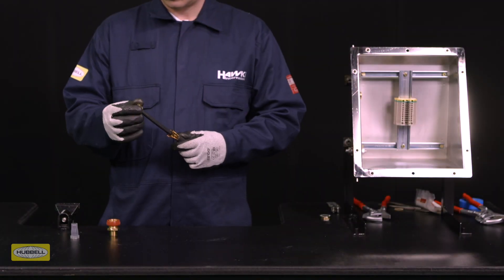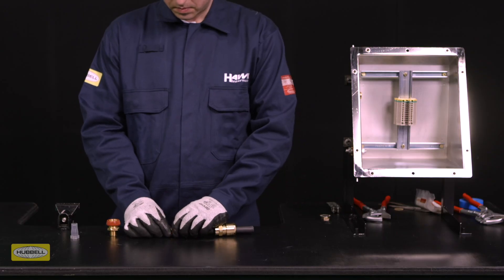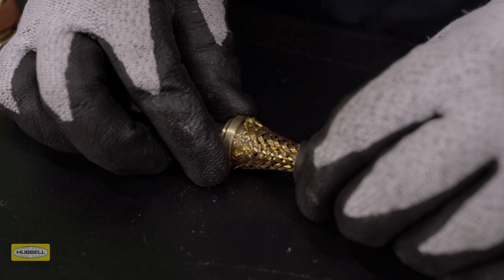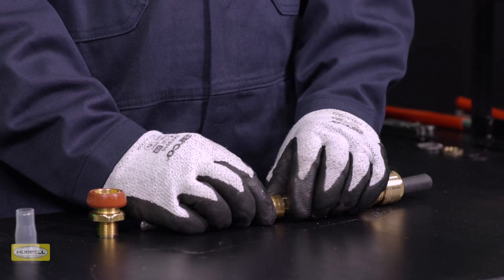Slide the spigot over the cable, taking care not to damage the rubber resin dam. Push the armor or braid up to the spigot shoulder. Slide the clamping ring up to the armor or braid by hand.